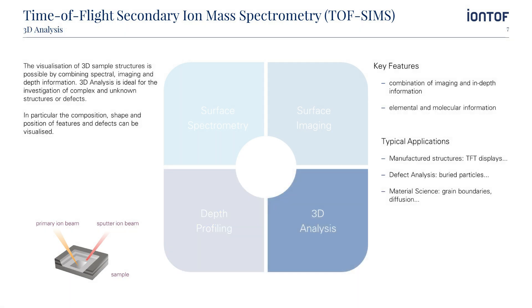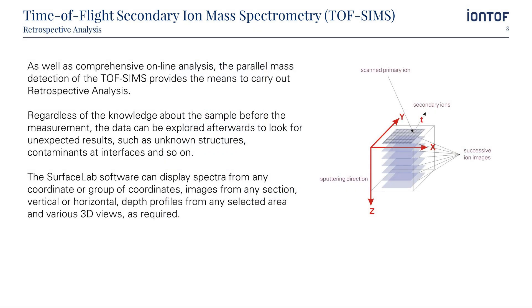The visualization of 3D sample structures is possible by combining spectral, imaging, and depth information. 3D analysis is ideal for the investigation of complex and unknown structures or defects. In particular, the composition, shape, and position of features and defects can be visualized. Key features include the combination of imaging and in-depth information, along with elemental and molecular information. The parallel mass detection of TOF-SIMS also provides the means to carry out retrospective analysis — exploring data afterwards to look for unexpected results, such as unknown structures or contaminations at interfaces.